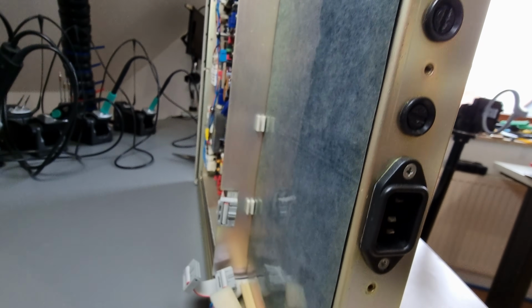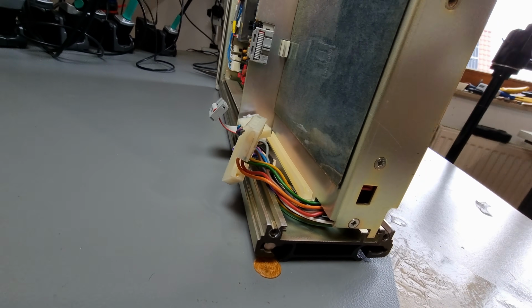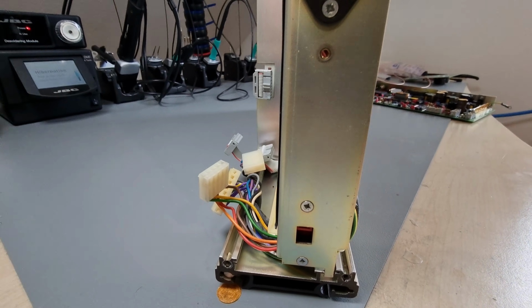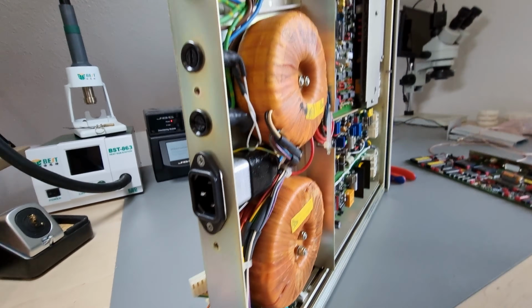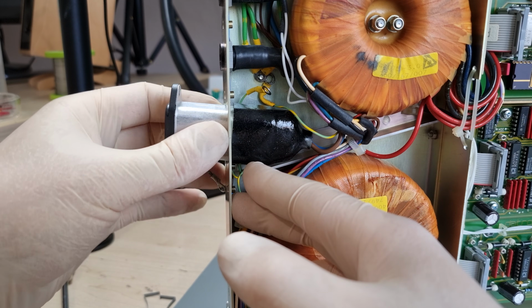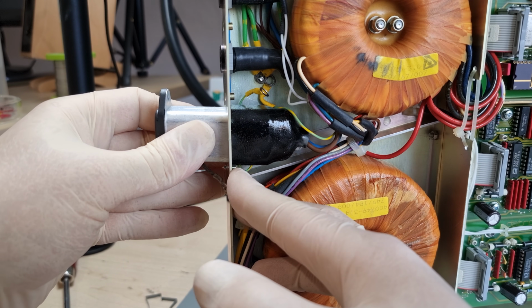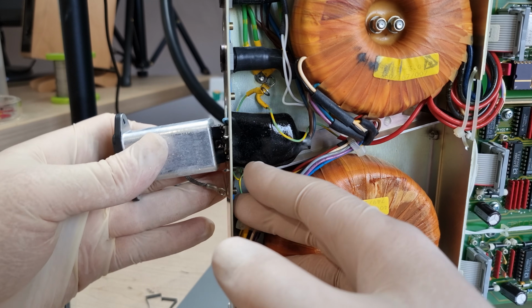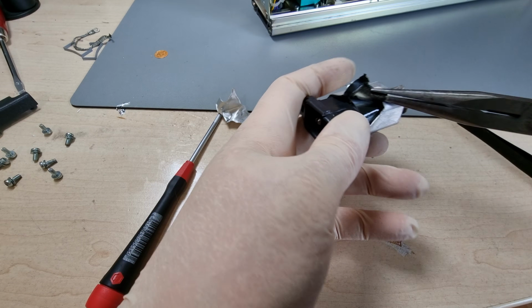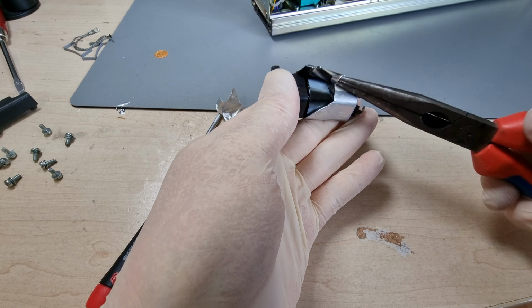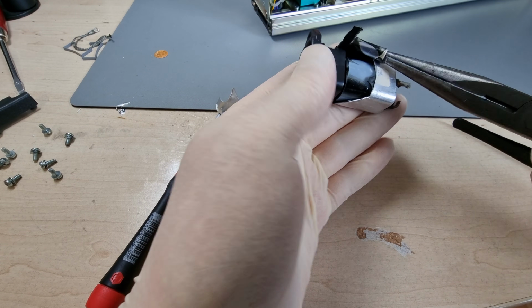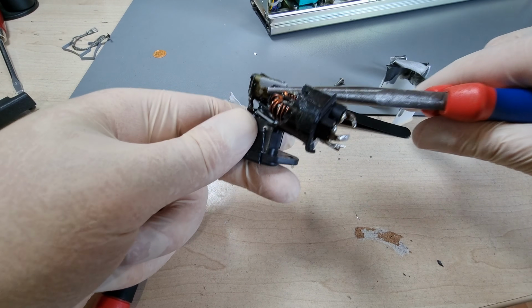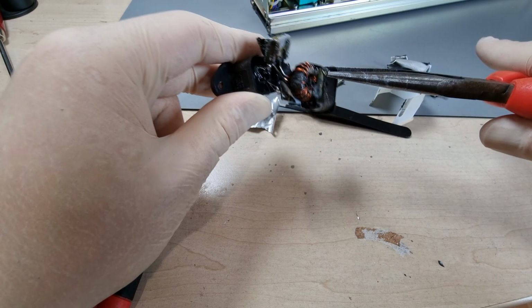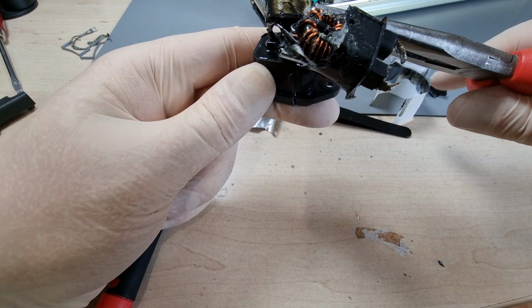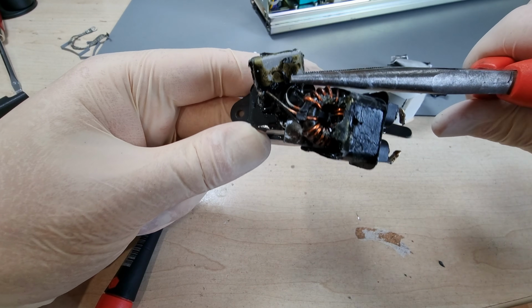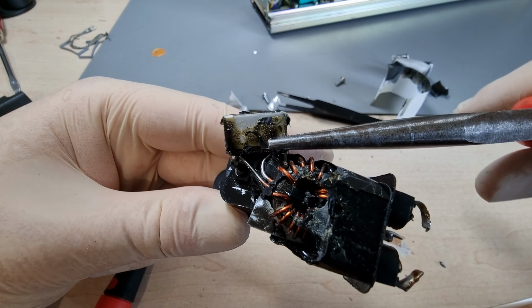Interestingly, this device has 2 IEC power outlets on the rear, for connecting its calibration victims to. At first I thought one of those 2 large toroidal transformers would be configured in a 1-to-1 configuration to provide some bonus isolation to those outlets, but no, they are just branching off of the main input. So this is purely a countermeasure against common mode effects from less than optimal mains connections. And this is why I preventively swap IEC filters. These epoxy Y-caps accumulate humidity, which leads to leakage currents, heat, and ultimately tar diarrhea being sprayed everywhere.